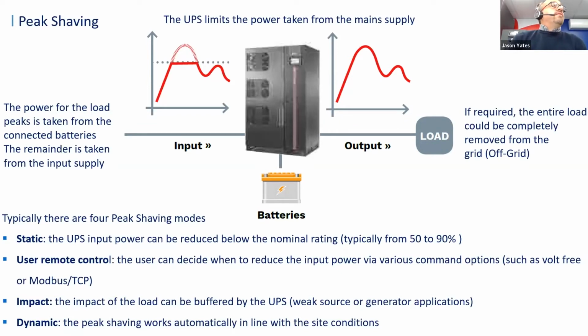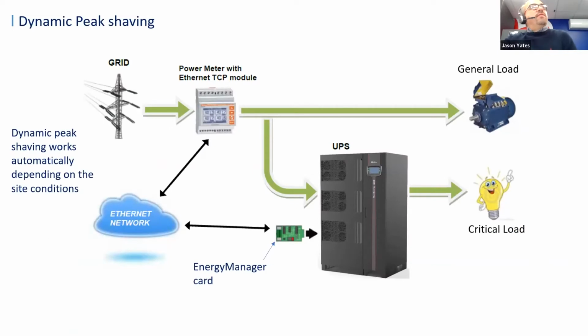You also then have impact load buffering, which is similar to peak shaving, but it can also operate where you've got a weak source or weak generators. If you have a site with a large impact of load in one step, then the UPS system can buffer and slow down the rate of change of that load onto the incoming main supply. And finally, and probably the most commonly used, is dynamic peak shaving, whereby the system works automatically in line with the site conditions.